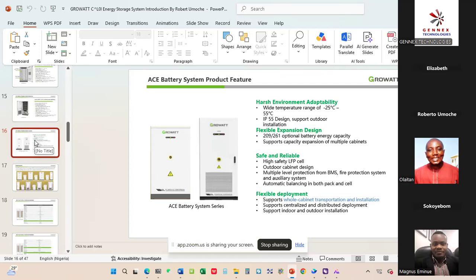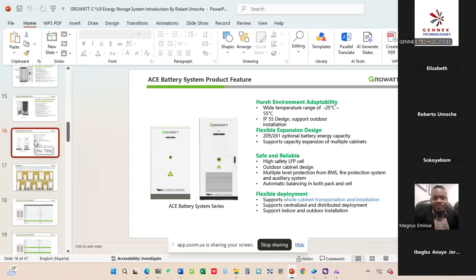I don't know if that is understandable. For the inverter, if you are doing a pure off-grid installation, the maximum that can be connected in parallel is 3 units, and 3 of them can be connected in parallel without issues. If you want to use it for grid tie purpose, the maximum you can go is 6. Grid tie means there will not be a need for a battery bank, you don't need storage, so you only need the PV and the grid. What this basically does is use the grid as a reference power.